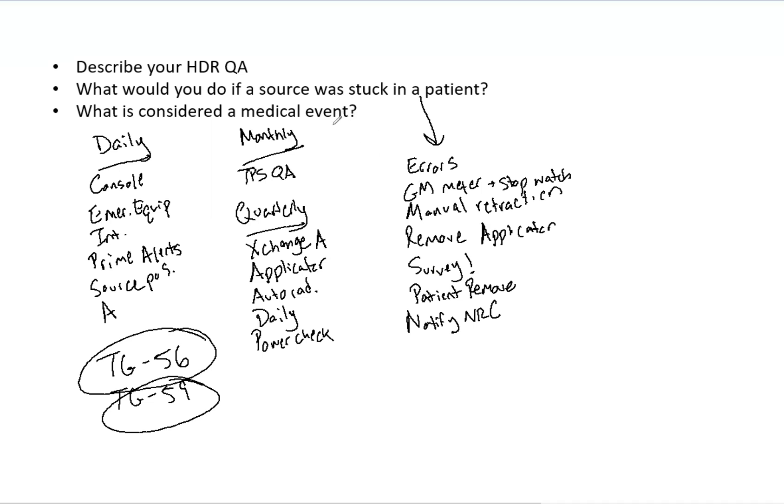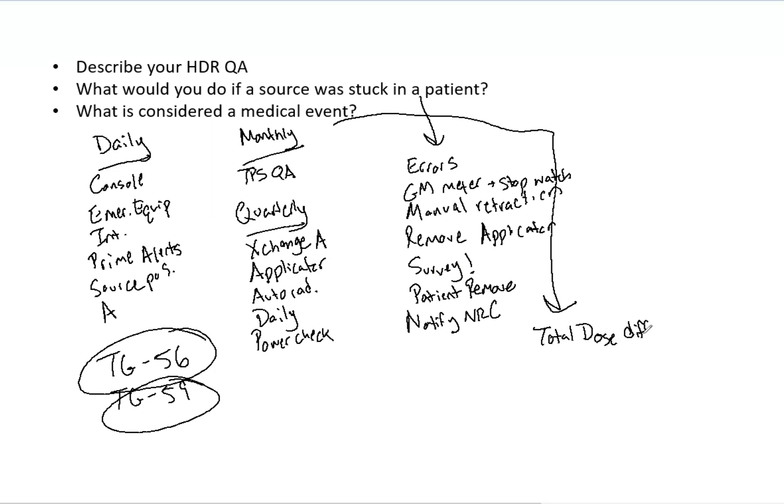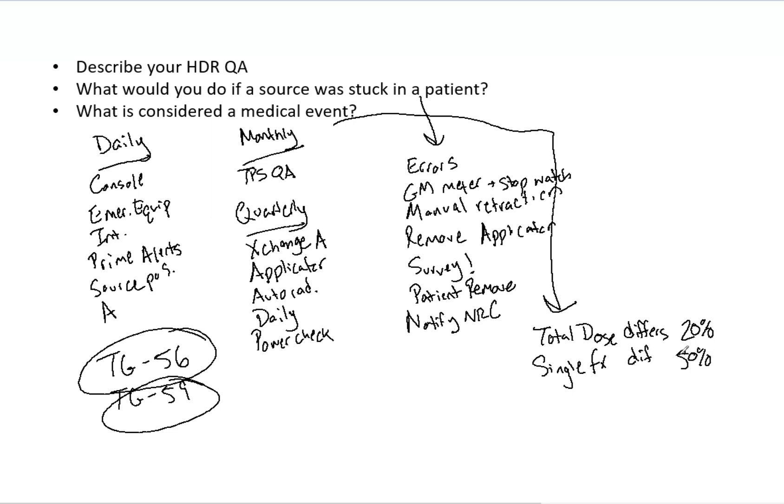So now what is considered a medical event? So two ways that you can determine this. So first of all, the total dose, if that differs by 20% or more, that is a medical event. Or if you have a single fraction and that dose differs by 50% or more, that is also a medical event. A wrong isotope, a wrong patient, or a wrong site is also considered a medical event.